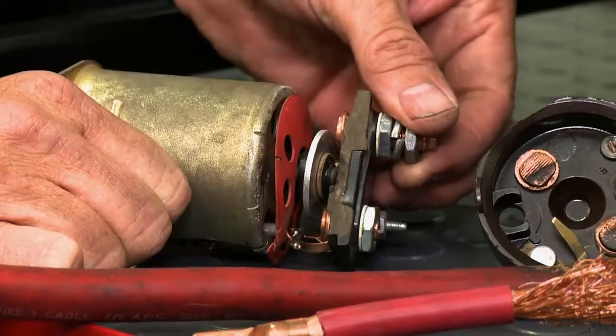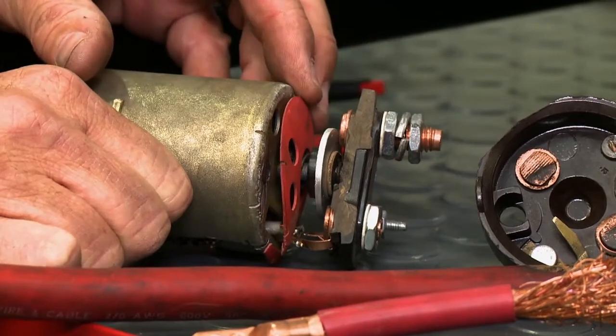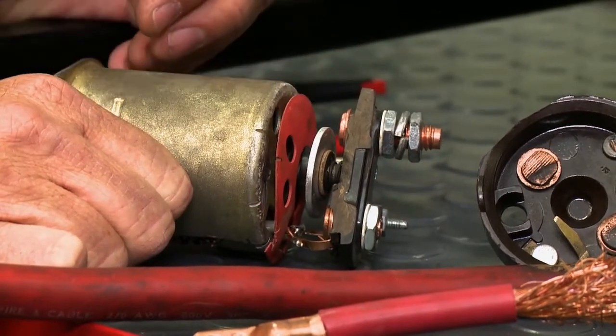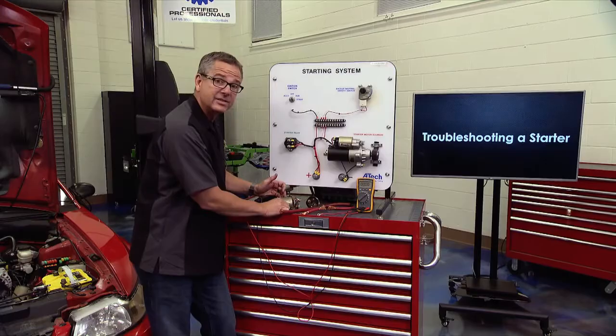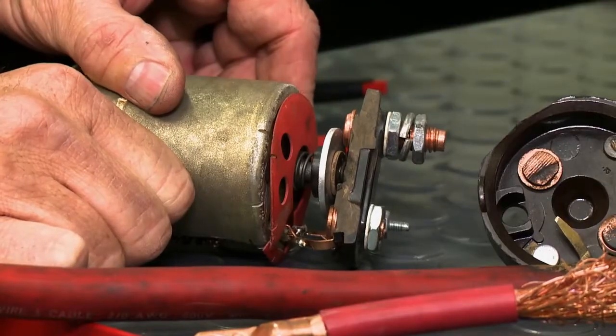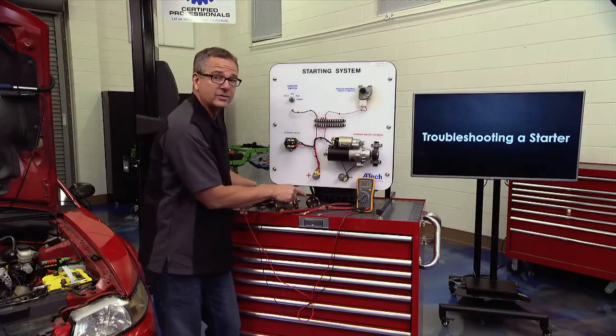If any of these lugs are loose, or this thing's not coming out, let's say you have a voltage drop prior to getting to this and you're not getting the magnetic induction you need, this thing's not coming out making a good contact, you're going to get burnt contacts like this. Well, guess what? There's your voltage drop right there.